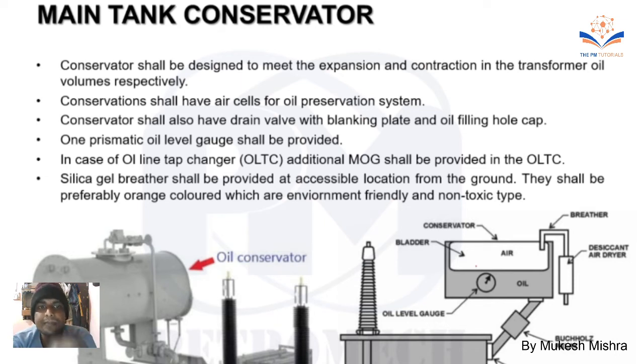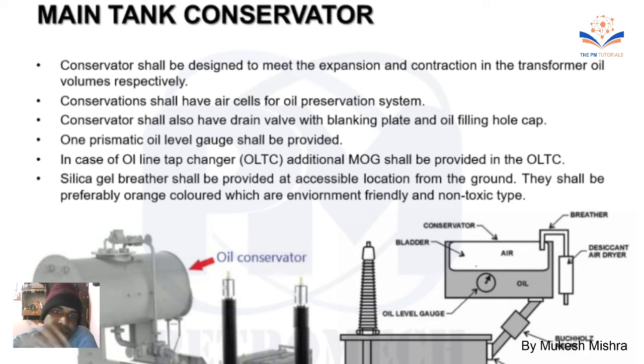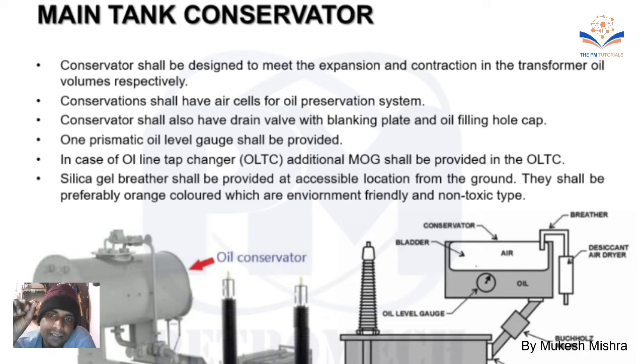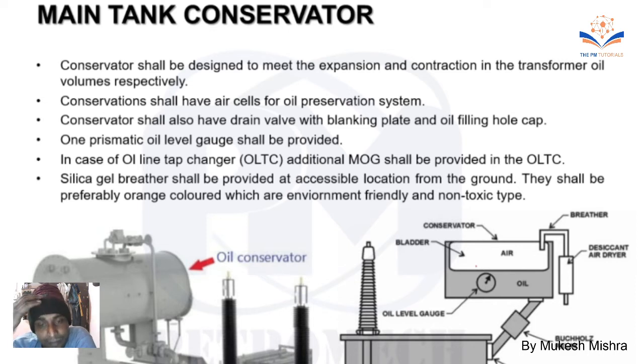The conservator system is designed to absorb air in the oil preservative system. Conservators will also have a drain valve with blanking plate and oil filling hole. One drain valve with blanking plate and one prismatic oil level gauge shall be provided.